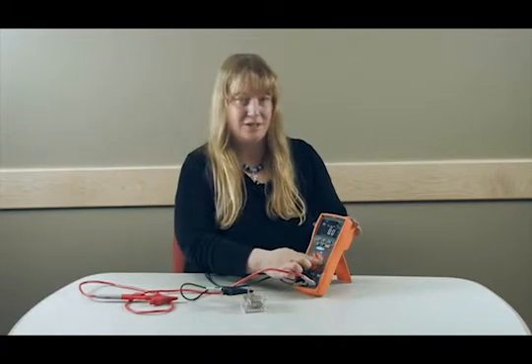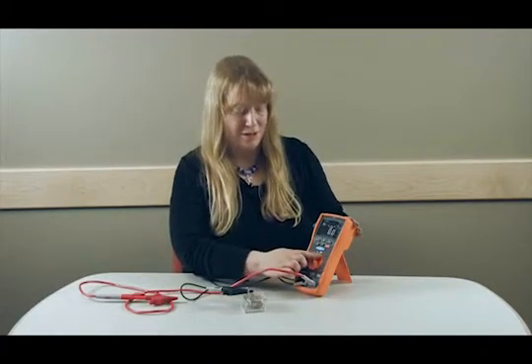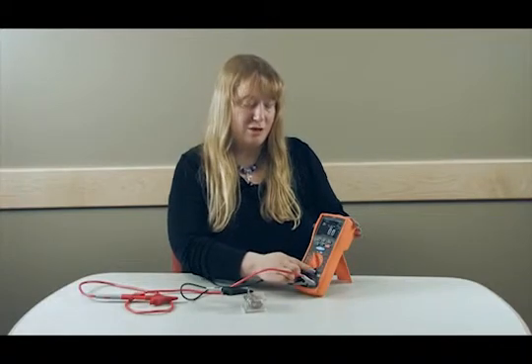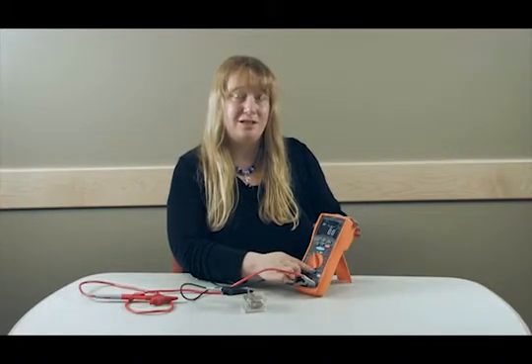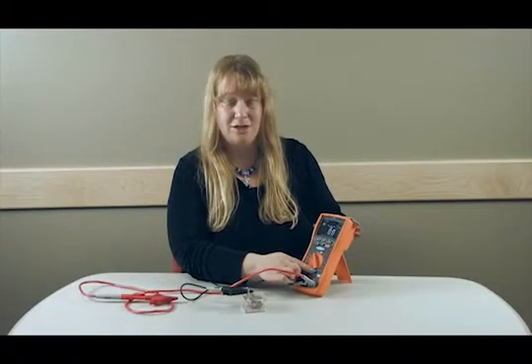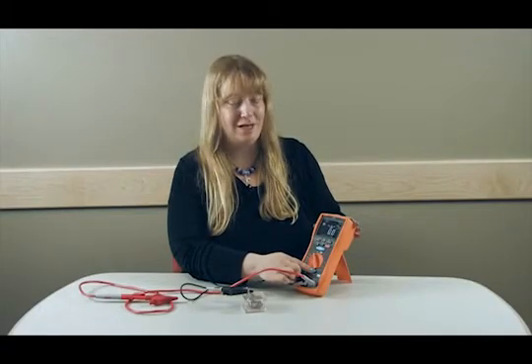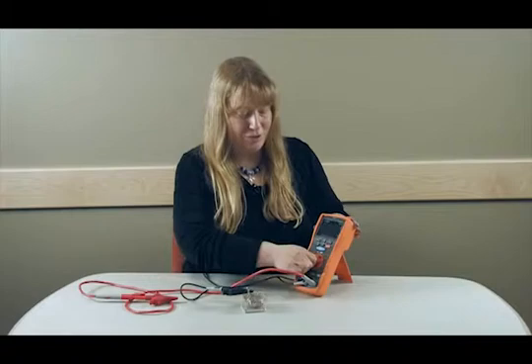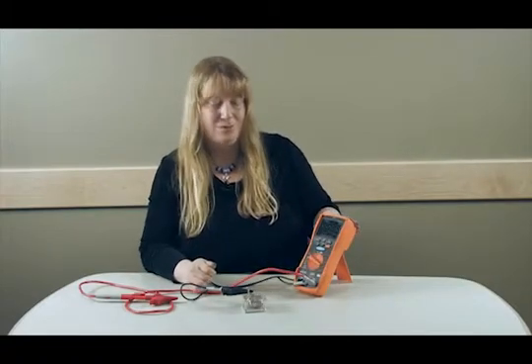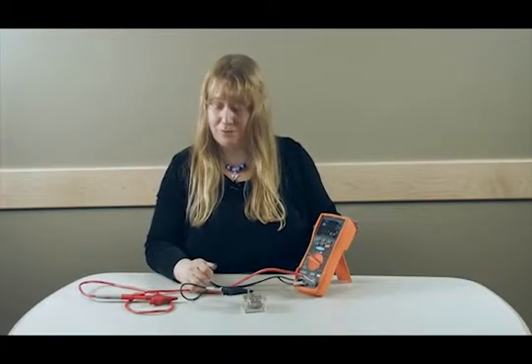Now we're going to switch over to the insulation measurement side. Selecting a meter that provides you with a wide variety of voltage ranges helps you to select the right voltage for testing your device under test. You don't want to get too large of a voltage. For this test we're going to use the 500 volt range.